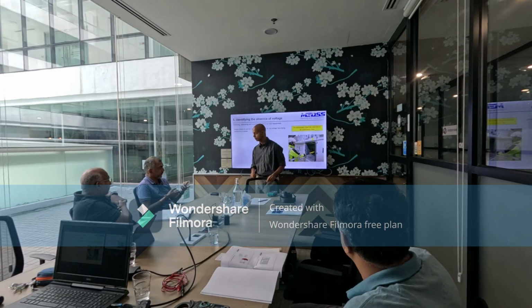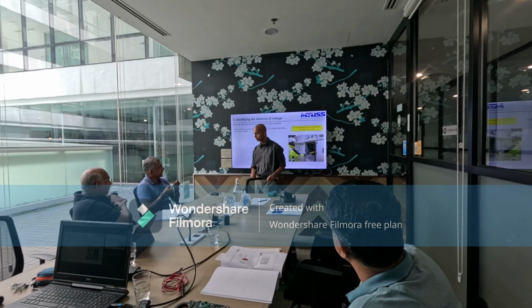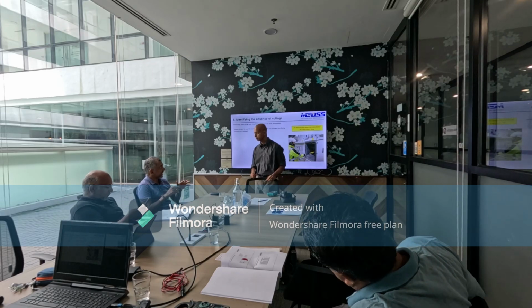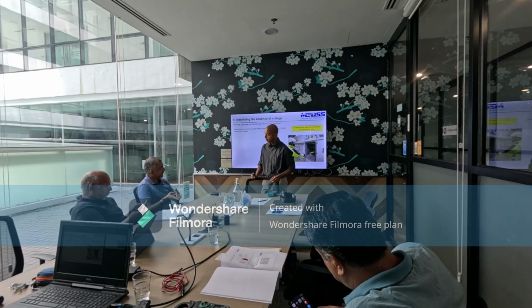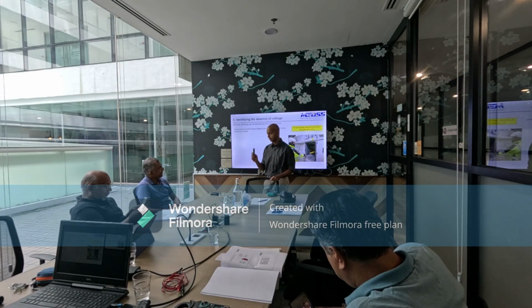I might be wrong, but one reason could be that for HV equipment, you must ensure it's working fine before putting it on HV, since if anything goes wrong the disaster can be even more severe than with LV. So far we haven't done this for LV since we sell phasing sticks, and I've trained staff on this procedure: use the probing unit to confirm the system works before going live, and test again before putting it back in the bag. That's already good practice, but LV testing is still required since most people don't deal much with LV unless they're in generation or distribution.